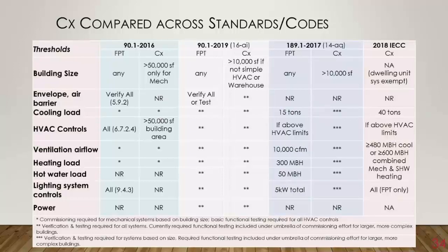If we move into 2019, so again, the verification testing is required for all systems. We've expanded the systems so that now everything is covered, at least everything with any controls or complexity, so that we've got that covered now. And then the commissioning, once we get above 10,000 square foot for a building, we do have to do verification and testing for the systems. There's certain required functional testing, and that rolls under the umbrella of commissioning for the larger, more complex buildings.